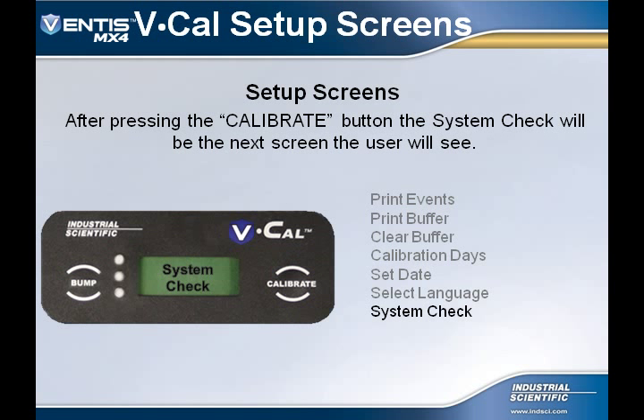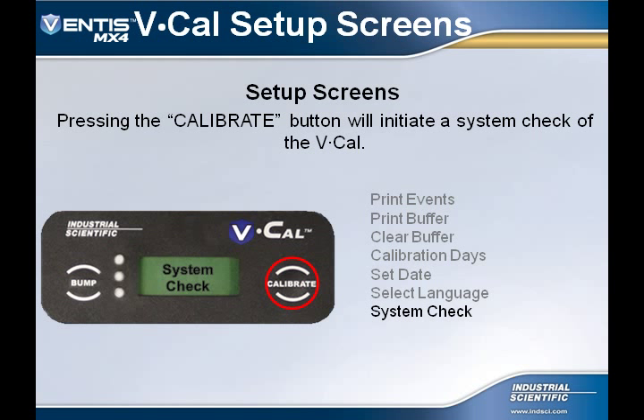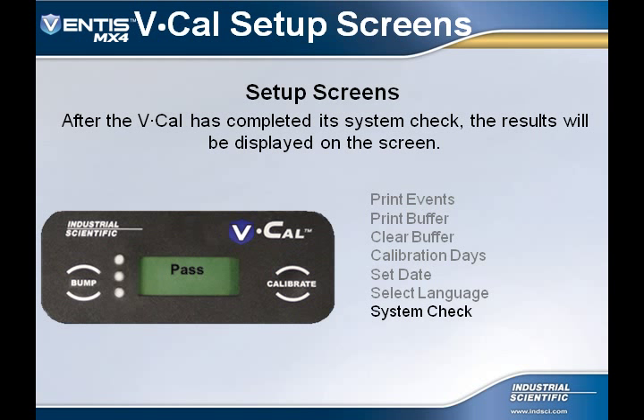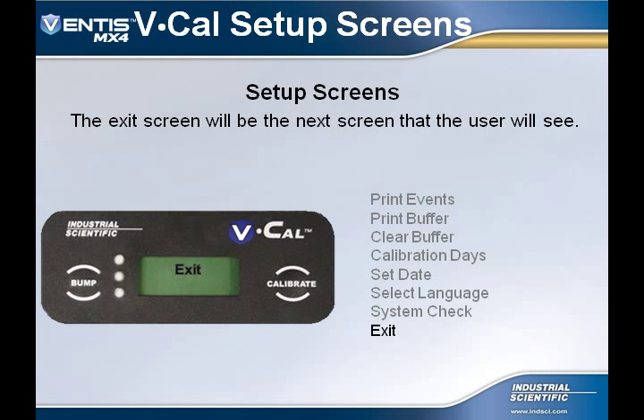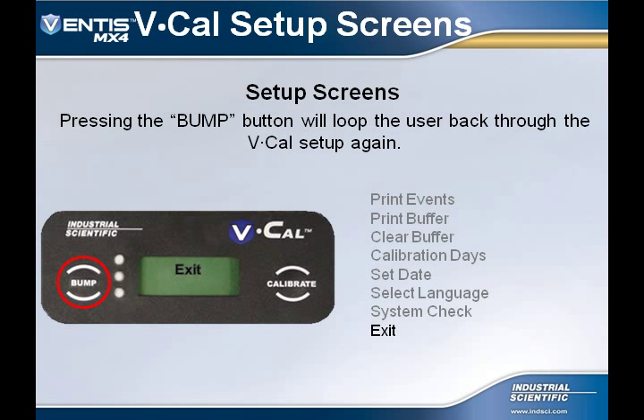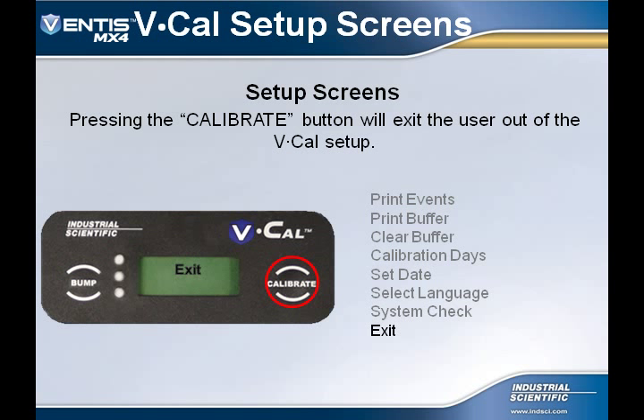The next option is System Check. This option allows the user to force the VCal to do a self-test. Pressing the calibrate button will initiate the system check. After completion of the system check, the results will be displayed on the screen. The next option is the Exit option. Pressing the bump button will allow the user to page back through the VCal setup screens. The Calibrate button will allow the user to exit the VCal setup screens. After pressing the Calibrate button from the exit screen, the VCal's display will return to the Ready screen.